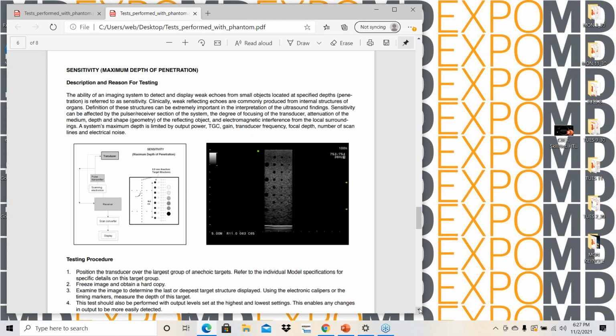And you maximize the depth that you can see, and you record the deepest recording you get. Doesn't matter if it's in penetration or resolution. If it's the deepest one, you record that one. That's the max penetration for the probe. And it tells you to do that. It's as simple as that procedure. It's not difficult. You can see, it doesn't show all the objects, but you can see we're doing the same type of testing here. That's probably the 4th. I think there's a bigger one over. Okay.